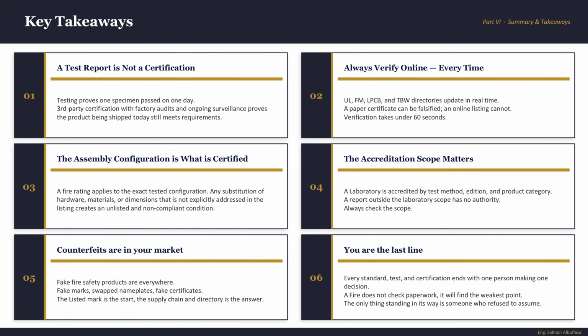And fourth, the accreditation scope matters. The accreditation scope is not for everything. They are authorized for a specific test method, specific standard edition, specific product categories. So if the product report cites a method outside their scope of work, that report has no authority. And fifth, counterfeits are on your market. People will always look for the cheaper alternative. And remember, the mark or the labeling is only the start. Always check the serial number and the database, and if in any doubt, do not approve, and always verify.